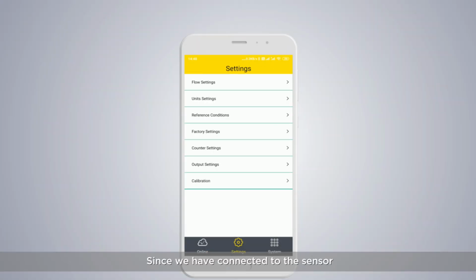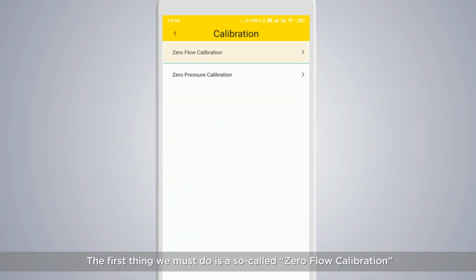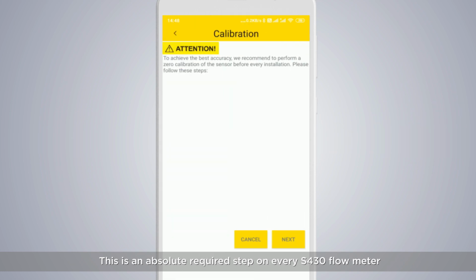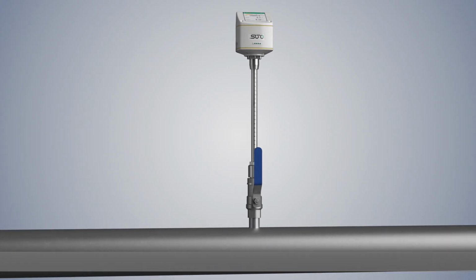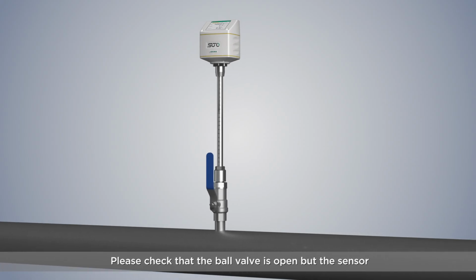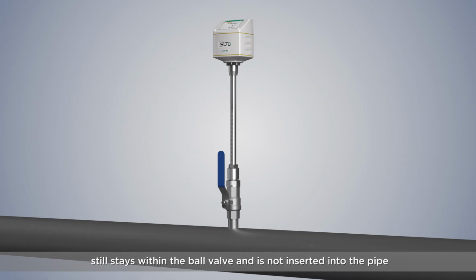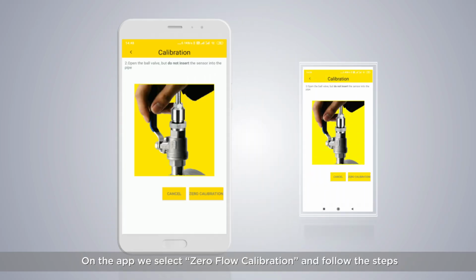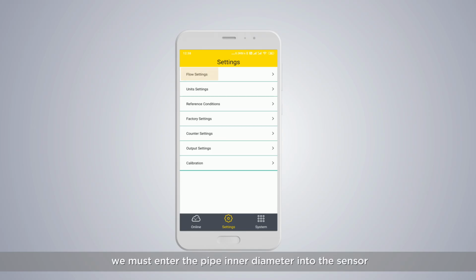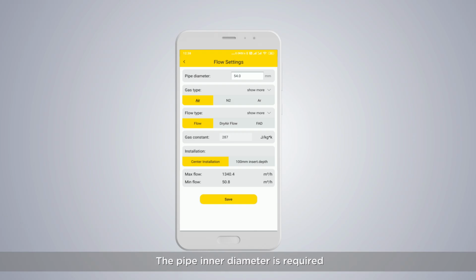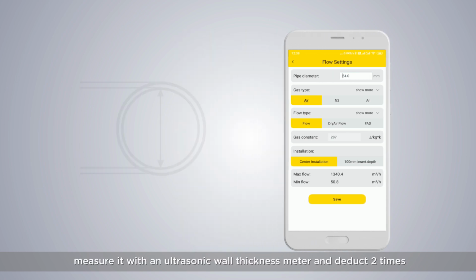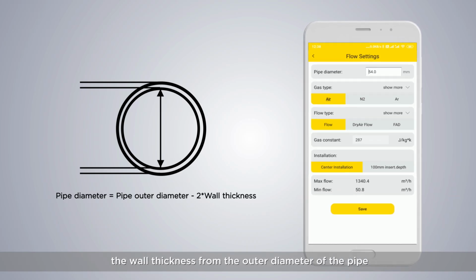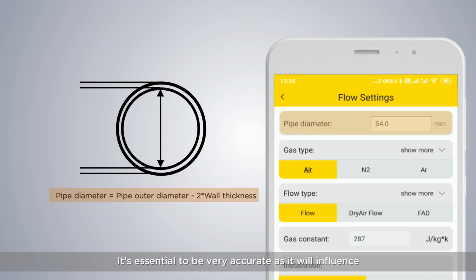Since we have connected to the sensor, we can now perform the settings. The first thing we must do is a so-called zero flow calibration. This is an absolutely required step on every S430 flow meter because the sensors must be calibrated before use. Please check that the ball valve is open, but the sensor still stays within the ball valve and is not inserted into the pipe. On the app, we select Zero Flow Calibration and follow the steps. After this is done, we must enter the pipe inner diameter into the sensor. The pipe inner diameter is required in order to perform the correct flow calculation. If you don't know it, measure it with an ultrasonic wall thickness meter and deduct 2 times the wall thickness from the outer diameter of the pipe. It's essential to be very accurate as it will influence the flow calculation significantly.